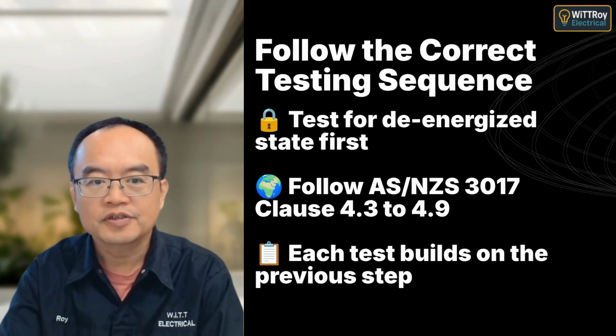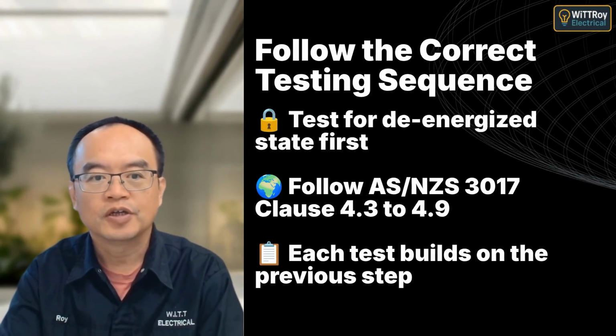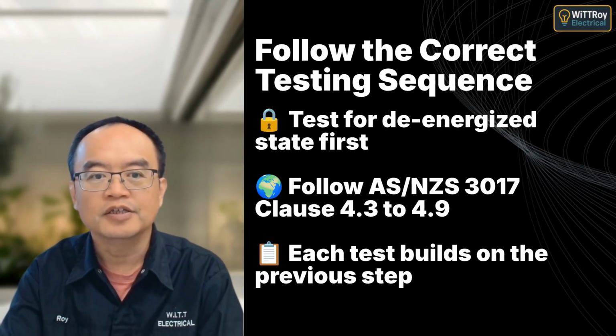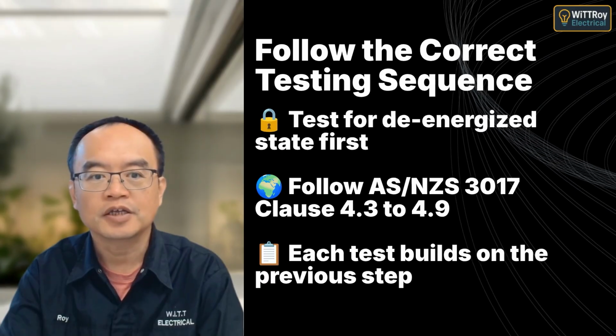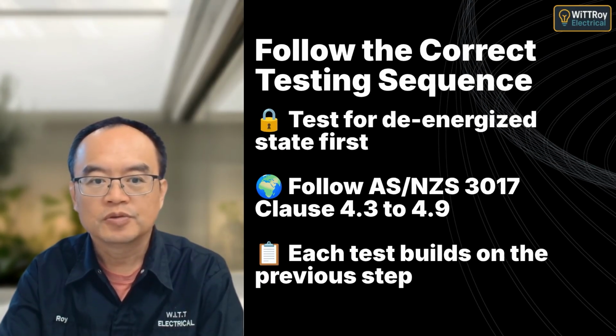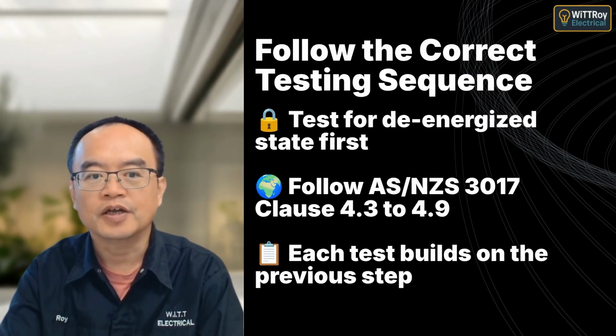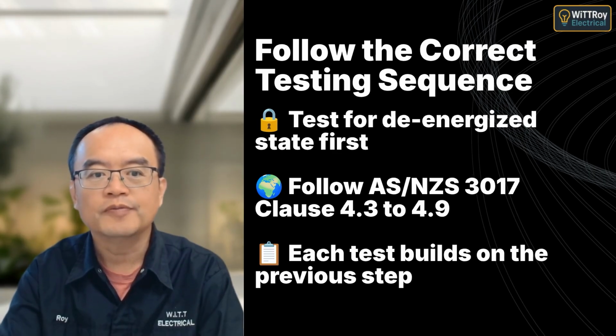AS/NZS 3017 sets out a specific test sequence to follow. Always start by testing that the installation is de-energized, then test earthing continuity, insulation resistance, polarity, earth fault loop, and RCDs in that order to avoid invalid results.